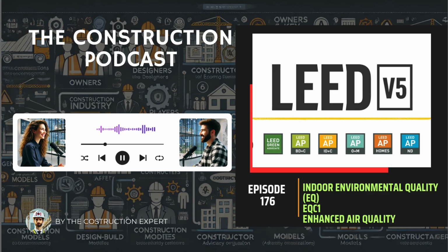Yes, 95%. That sounds like it means almost total coverage of where people actually spend their time. What is the engineering complexity involved in actually verifying that 95% threshold is met? That sounds tricky. Verification of that 95% is definitely the commissioning challenge. It demands meticulous documentation during design and then rigorous testing and balancing during commissioning after construction. So boots on the ground with airflow meters. Absolutely. You can't just assume based on the design drawings that every room gets its calculated share. You need actual airflow readings taken at the supply air terminal units in a representative majority of the regularly occupied spaces: offices, conference rooms, classrooms, labs, whatever the building function is.